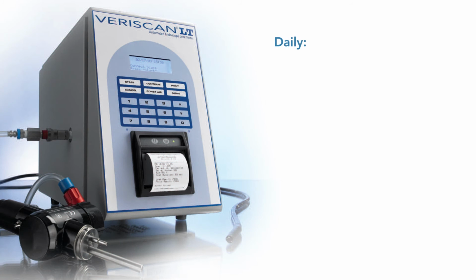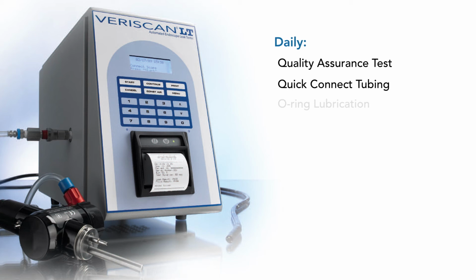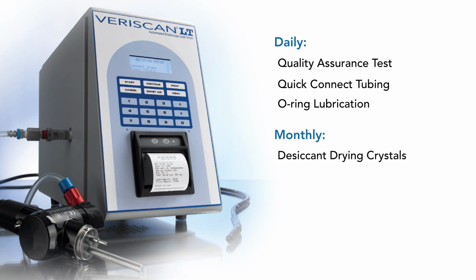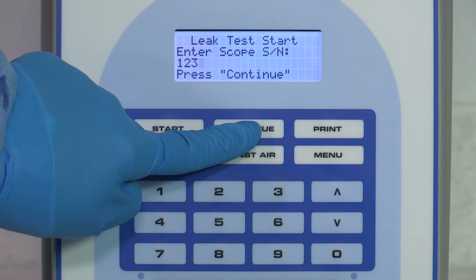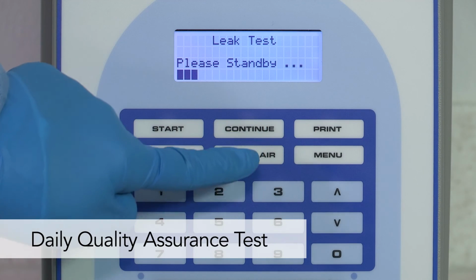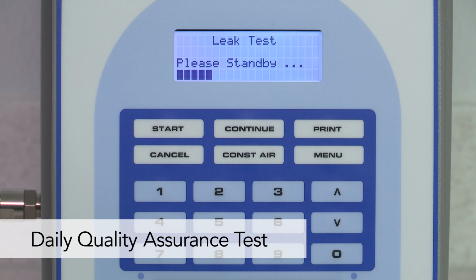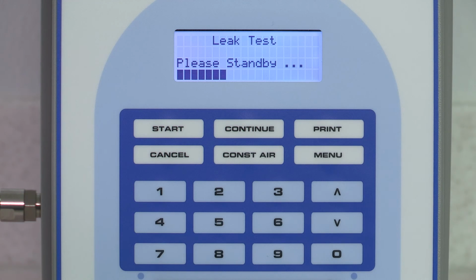The VERISCAN Leak Tester requires a minimal amount of regular maintenance and care to keep the unit in excellent operating condition. Let's review each of these maintenance areas. To verify proper operation, the daily quality assurance test must be performed prior to the first use of the day. This test ensures the internal integrity of the unit and its ability to properly sense an endoscope leak.